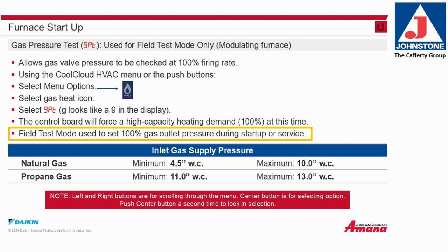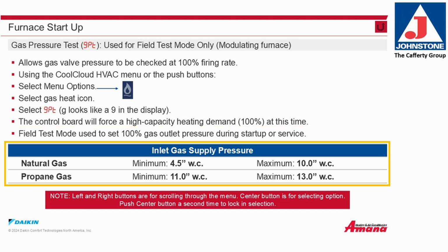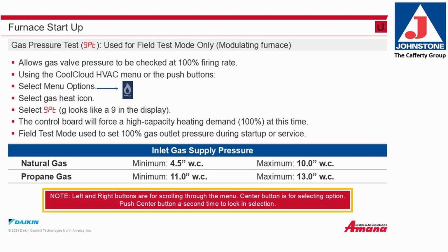Field test mode is used to set 100% gas outlet pressure during startup or service. Inlet supply gas pressure for natural gas: minimum 4.5 inches of water column, maximum 10 inches of water column. For LP gas, minimum 11 inches of water column, maximum 13 inches of water column. Please note, the left and right buttons are for scrolling through the menu. The center button is for selecting the option. Push the center button a second time to lock the selection.